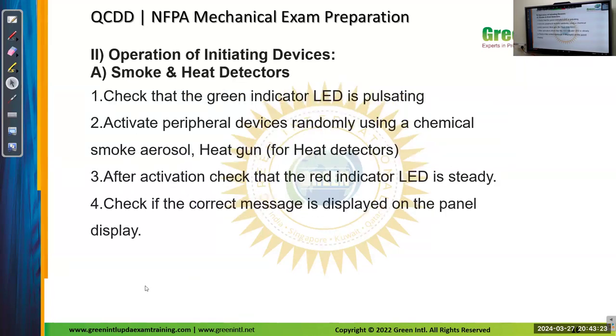So third is operation of initiating devices. Once the output is being given from the control panel, we will check that the smoke detectors and heat detectors are detecting the signals. Check that the green indicator LED is pulsating, activate the peripheral devices randomly using a chemical smoke aerosol, and after activation, check the red indicator LED is steady. If the correct message is displayed on the panel, then we can say that the smoke and heat detectors are working or not.